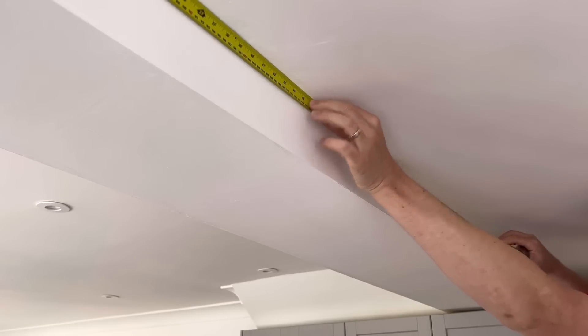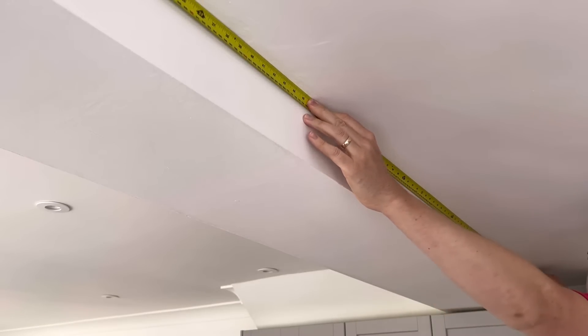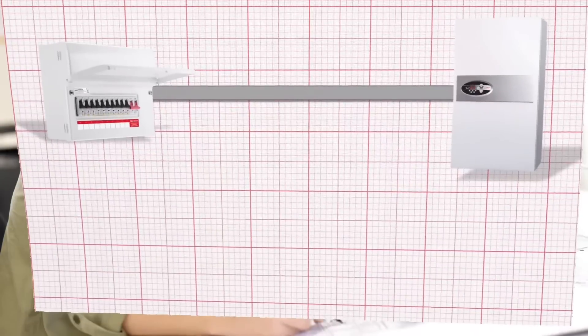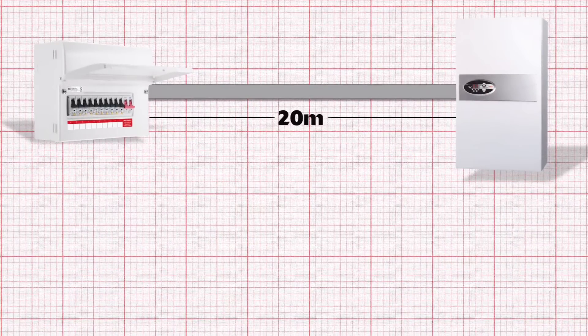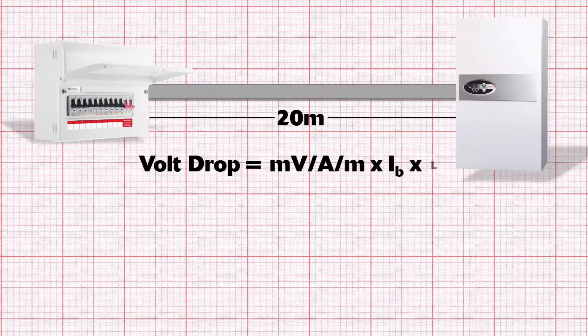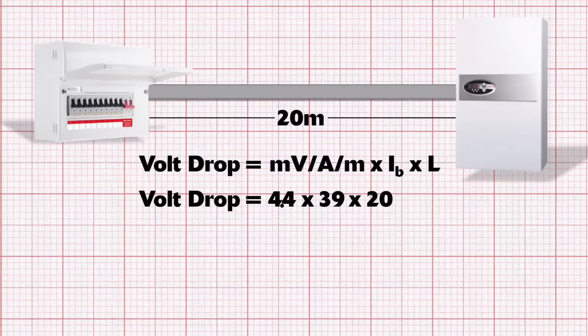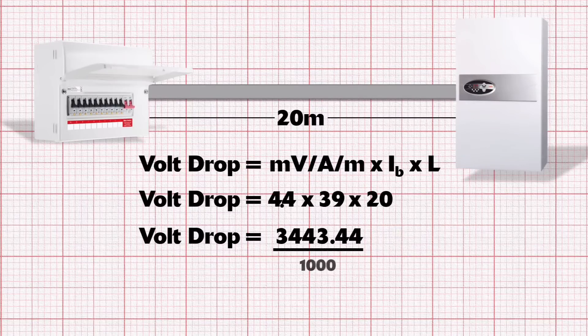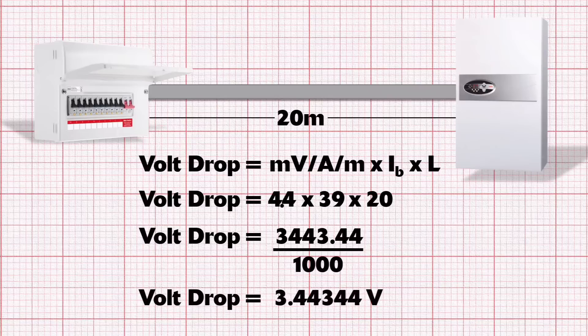If it's a new property, you can measure the length off the building plan using tools in CAD drawings. For our boiler circuit, the cable is 20 metres long. So we take our value from Table F6 of 4.4 millivolts, multiply it by the design current of 39.13 amps, and then multiply by the length of 20 metres. This gives us a value of 3,443.44 — but remember that this is in millivolts. To find the value in volts, we divide the answer by 1,000, giving us 3.44 volts.